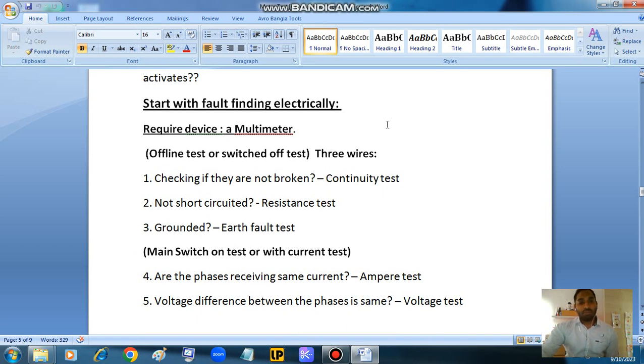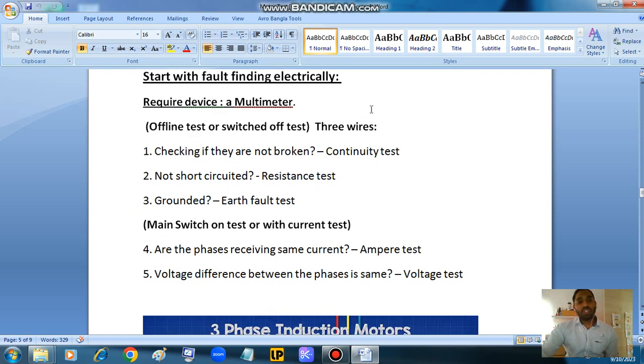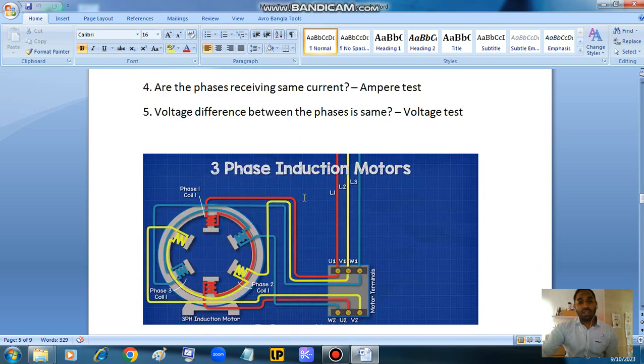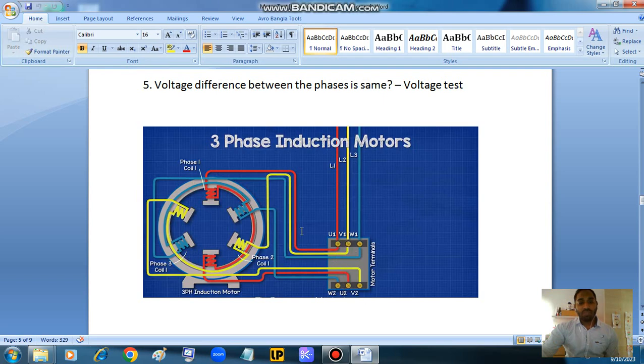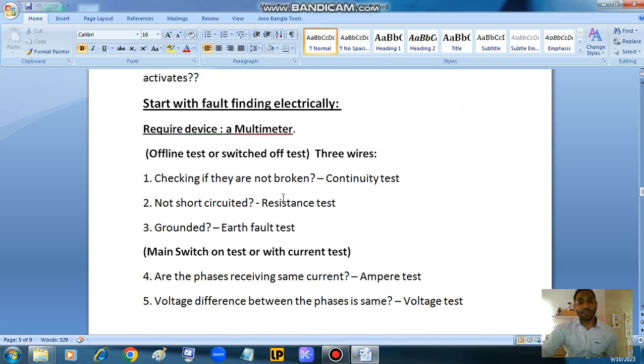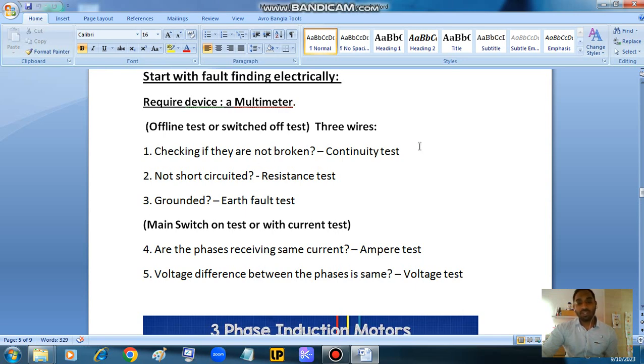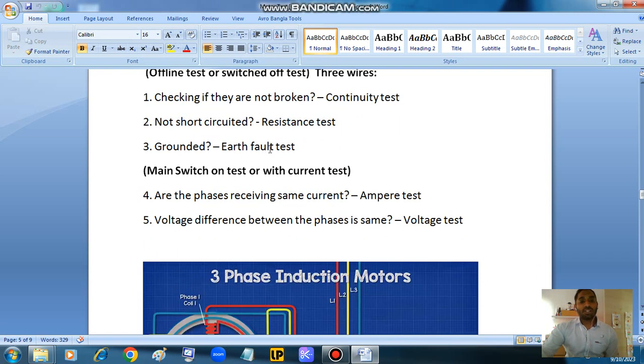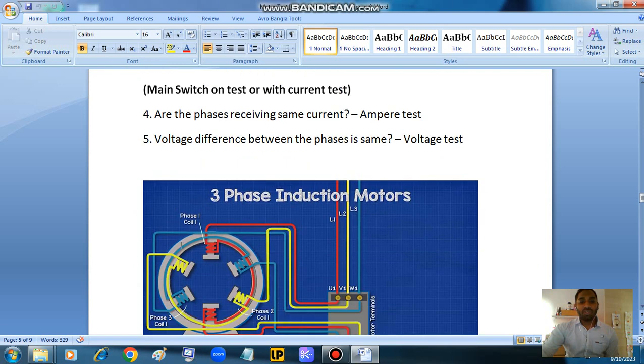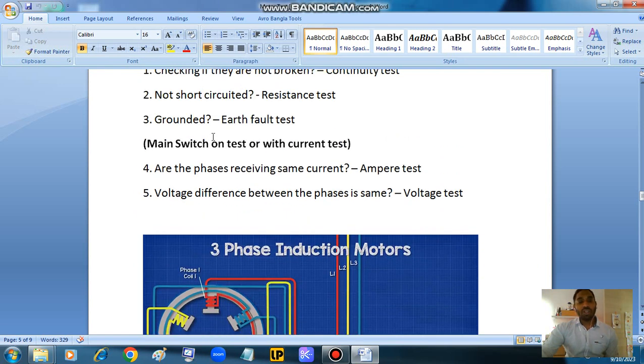To test a motor, we require a multimeter. There are two types of test: offline test and online test. In the offline test, for the wires U1, U2, V1, V2 and W1, W2, we have to check that the wires are not broken, which is the continuity test. The multimeter has to be set to continuity. Then we check that the wires are not short circuited, not connected to each other. This is the resistance test. The multimeter has to be set to resistance. Earth fault test means checking that none of the wires is connected to the motor body. This is a huge failure of the motor. It is a fatal cause.